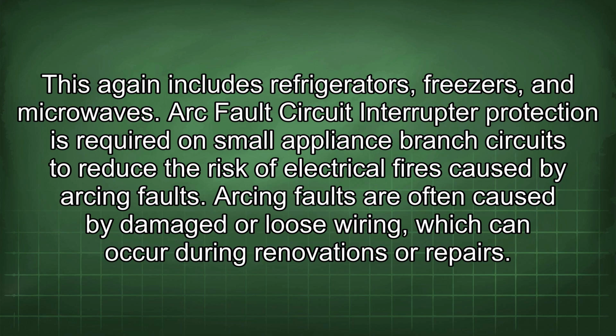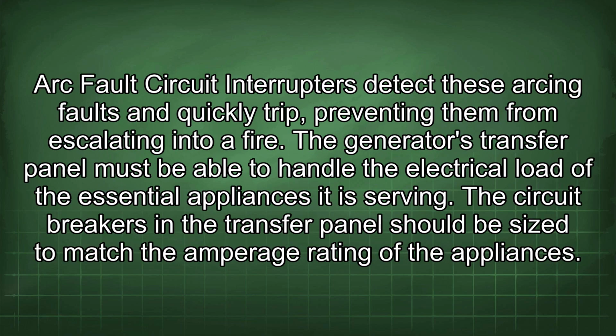Arc fault circuit interrupter protection is required on small appliance branch circuits to reduce the risk of electrical fires caused by arcing faults. Arcing faults are often caused by damaged or loose wiring, which can occur during renovations or repairs. Arc fault circuit interrupters detect these arcing faults and quickly trip, preventing them from escalating into a fire.